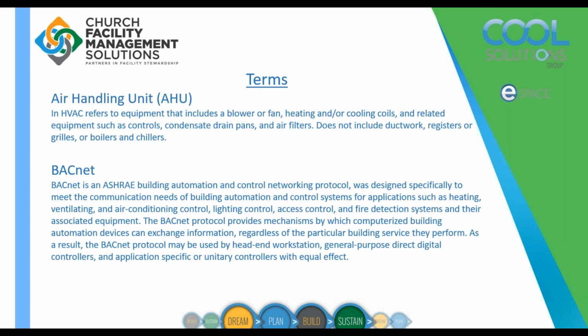I say theoretically and I say supposed to. Just because it's BACnet does not mean it's going to communicate well. But if it is BACnet or it will accept BACnet inputs, that is better than proprietary systems. So if you're speccing systems, that's a great question to ask. What language does it speak, and can it play nice with others?